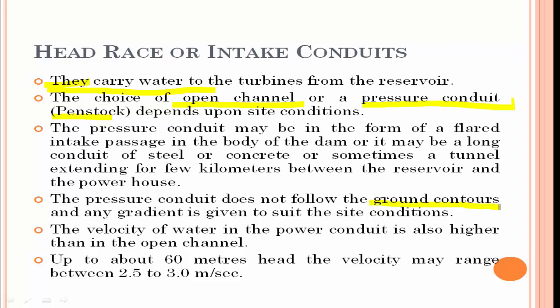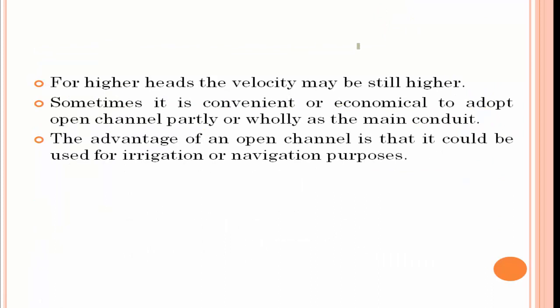The pressure conduits do not follow the ground contours, so we can have some deviation in the pipeline connection. The velocity of water in the pressure conduits is greater than in the open channel. Up to about 60 meters head of water, the velocity may be in the range of 2.5 to 3 meters per second. For higher heads, the velocity may be higher. Sometimes it is convenient or economical to use an open channel as the main conduit, and the advantage of an open channel is that it can also be used for irrigation or navigation purposes.